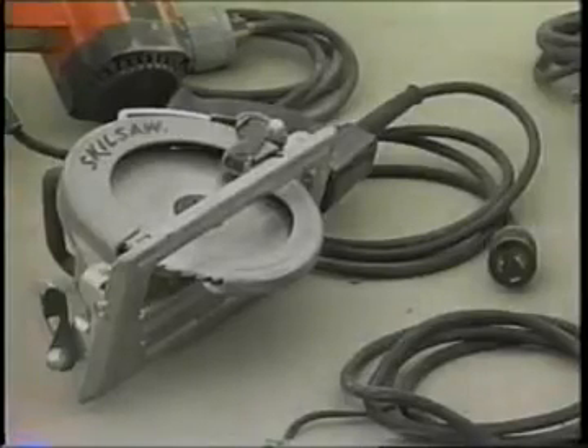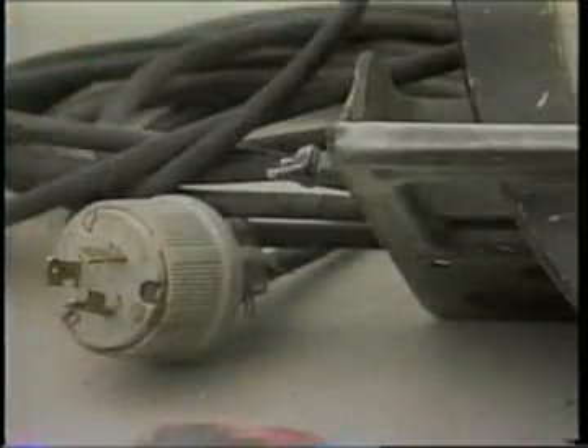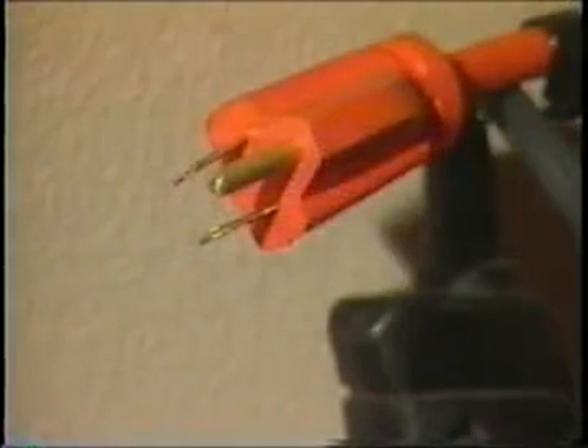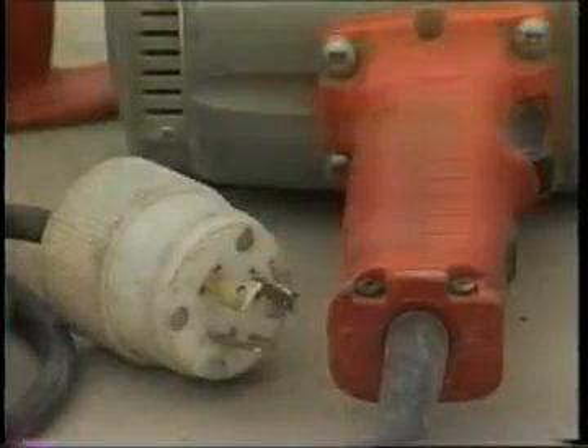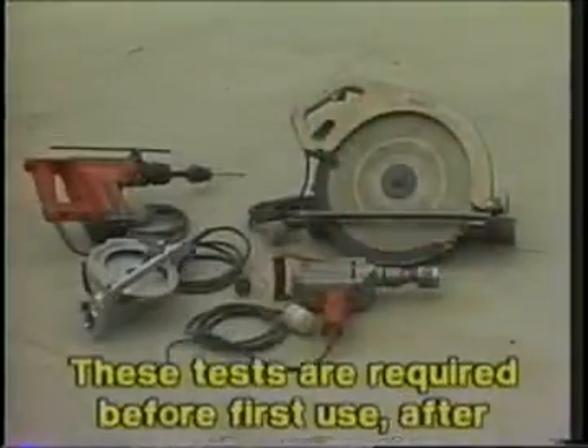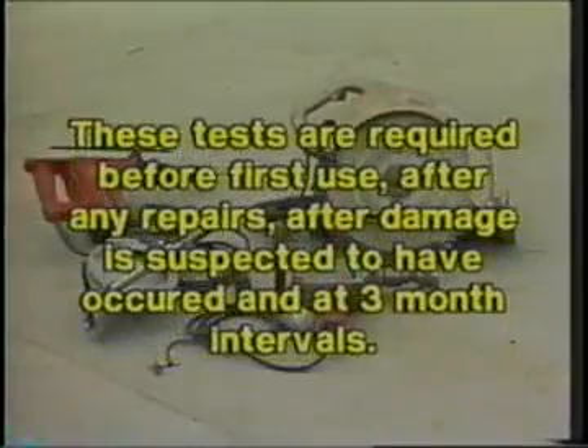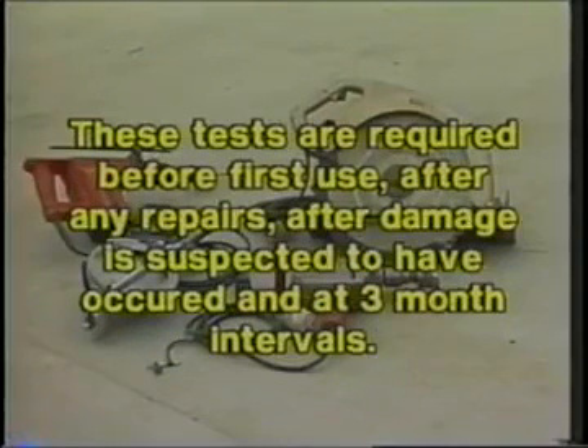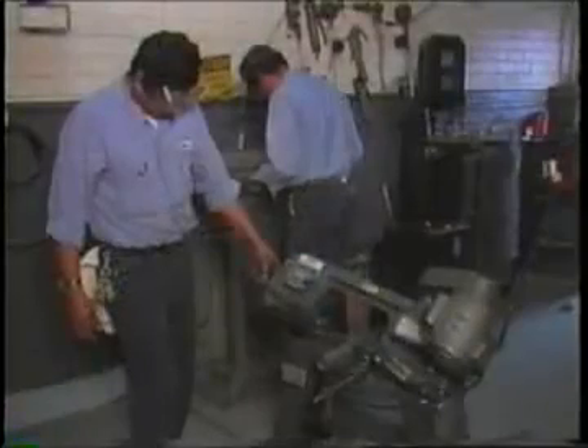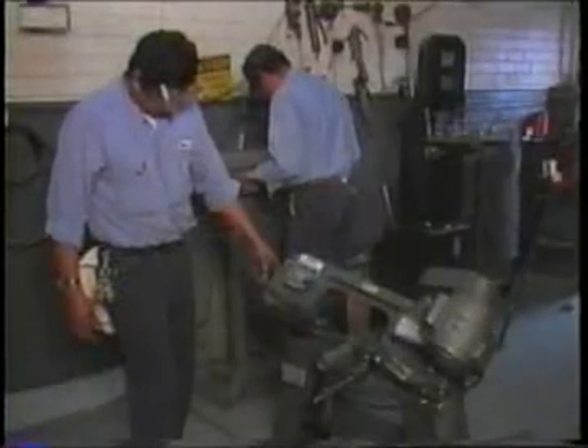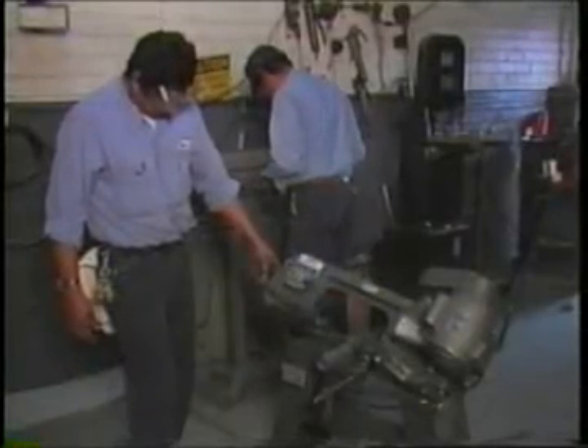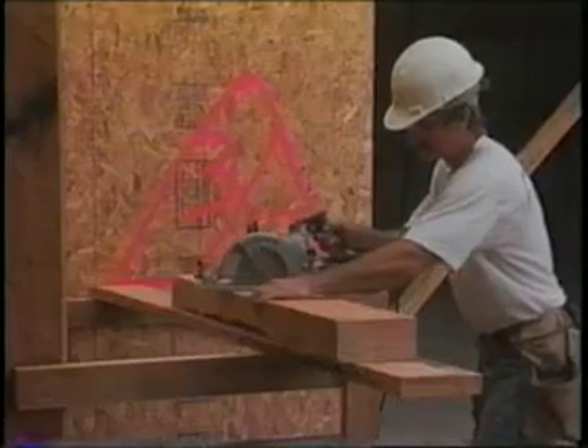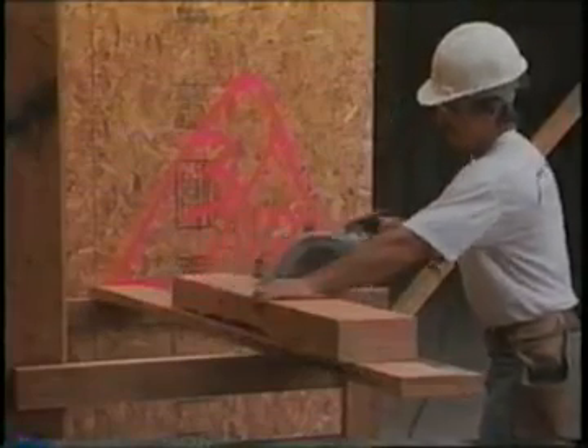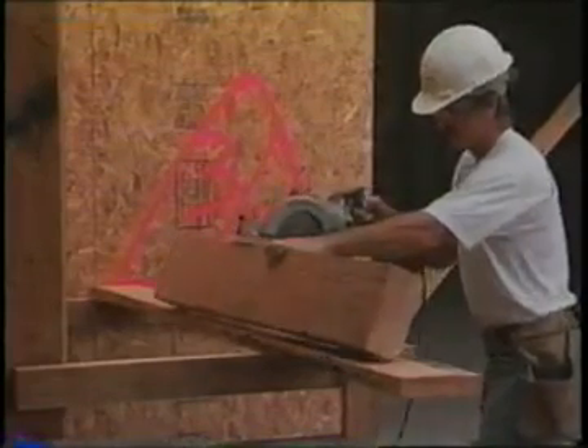The other test must be performed on receptacles and plugs to ensure that the equipment grounding conductor is connected to its proper terminal. This test can be performed with the same equipment used in the first test. These tests are required before first use, after any repairs, after damage is suspected to have occurred, and at 3-month intervals. If the cord sets and receptacles are essentially fixed and not exposed to damage, these may be tested at 6-month intervals. These testing and record-keeping requirements may be somewhat time-consuming, so most employers choose to use the GFCI system of protection.